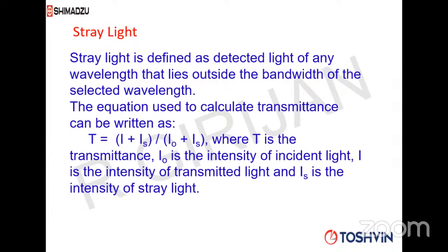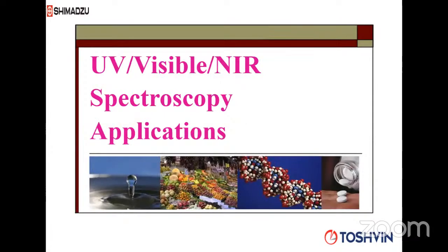They say Straylight is 0.00001%, like that they say. But nobody will write Straylight is 0%, 0.0%. That nobody can write. We have to give some value. If Straylight is more, what will happen? Your sensitivity will reduce.